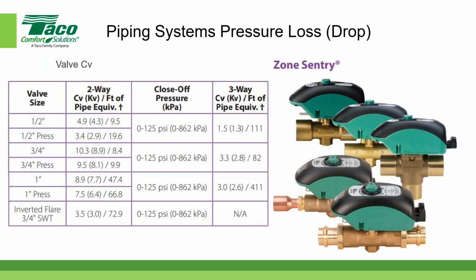In fact, here we have a little table. Another segue. And this is the zone sentry valve manufactured by Taco. And this little table tells us what the CV value is. So we're going to take, for example, a 3/4 inch diameter valve. The first value is CV, the one in parentheses is KV, and the last one is the feet of equivalent length, all right? So in this case, it's 10.3.